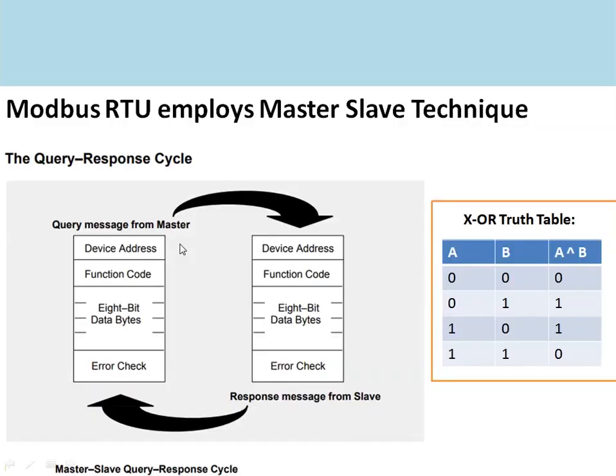This protocol employs a master-slave technique. The master sends the query and the slave responds to that query. The master can be an HMI or SCADA system, and the slave can be a PLC. Whenever the master asks for some data, it sends it in the form of bytes: the device address corresponds to the address of the PLC, the function code indicates whether it is digital input or analog input.